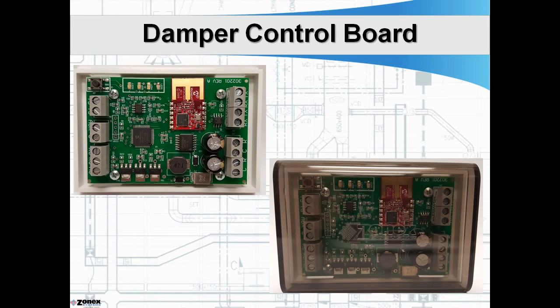The communicating damper board is housed and protected, as you can see, providing easy access and clearance to the wiring terminals on this board located on each zone damper.